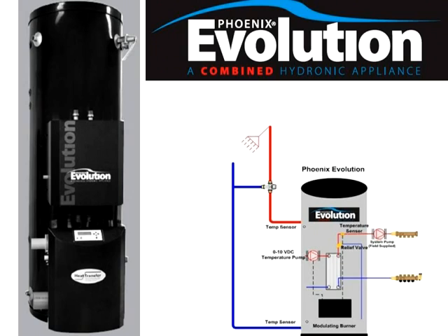Now, one of the characteristics of this particular appliance is its capacity is number one water heating, meaning it gives a lot of hot water on demand in high peak load conditions. And it also does the space heating. Given our load profiles, that's really the sequence of load that we see. And that's why this particular system is set up so well for that. Of course, when you have a boiler and an indirect, you sometimes have to oversize your boiler in terms of getting your domestic hot water requirements, whereas there's absolutely no penalty for doing so in this high mass configuration.